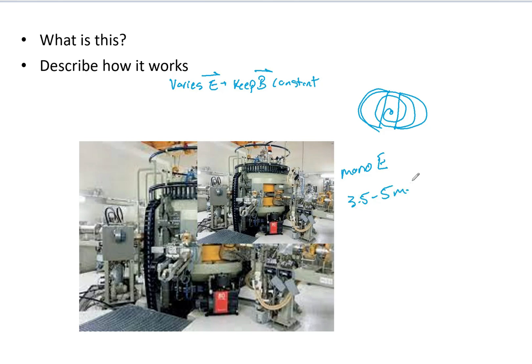And one of the disadvantages are that you get higher neutron contamination with the use of energy degraders that change the proton range. So you get one energy, if you want something else you can use a degrader, but that is going to increase the neutron contamination.